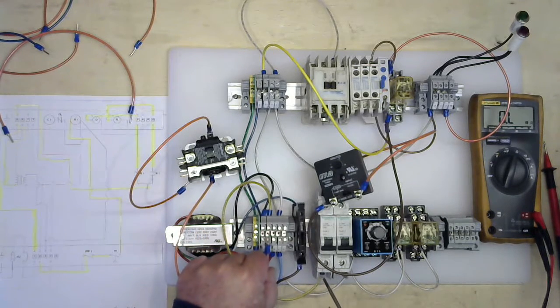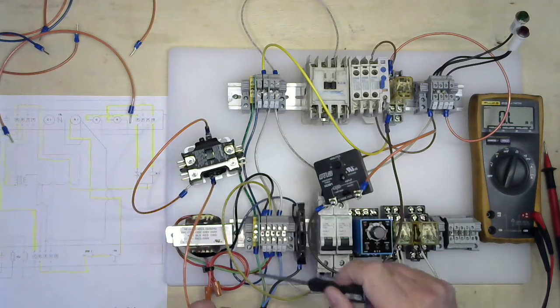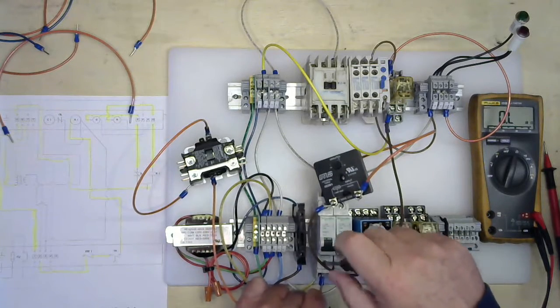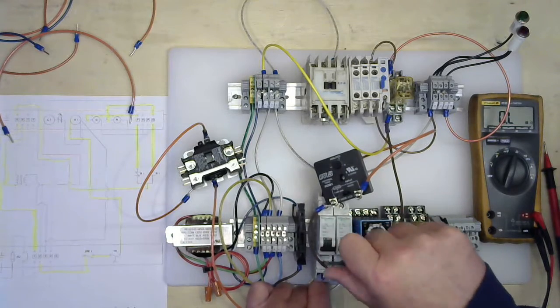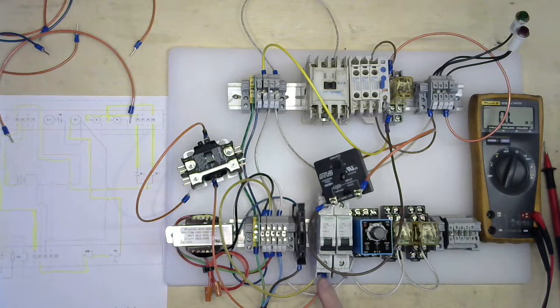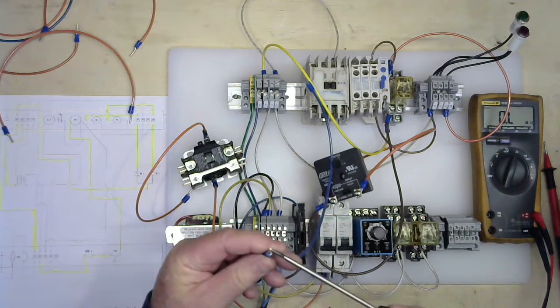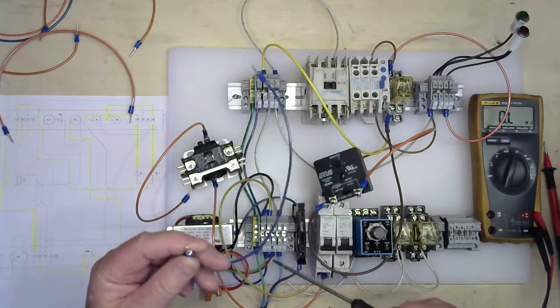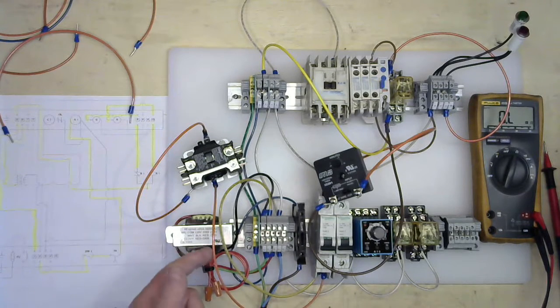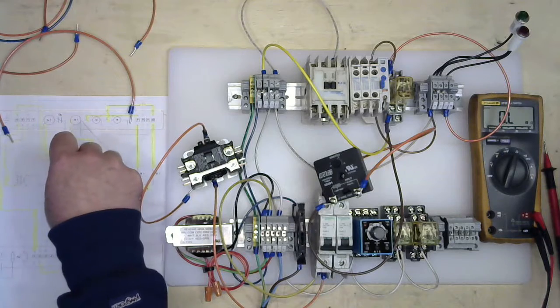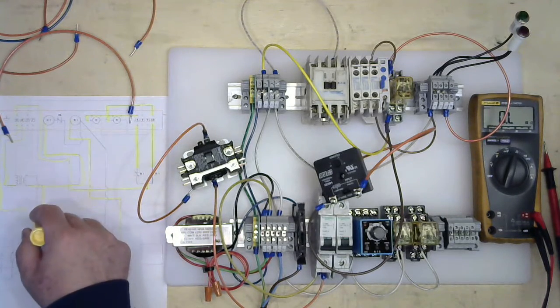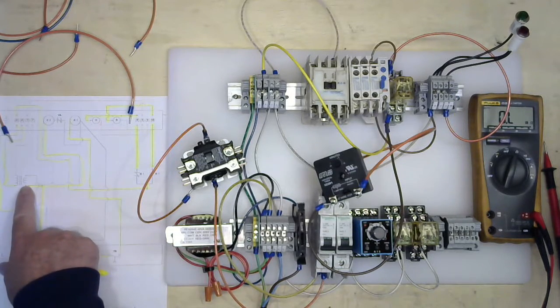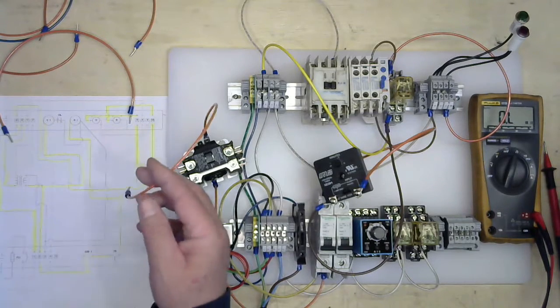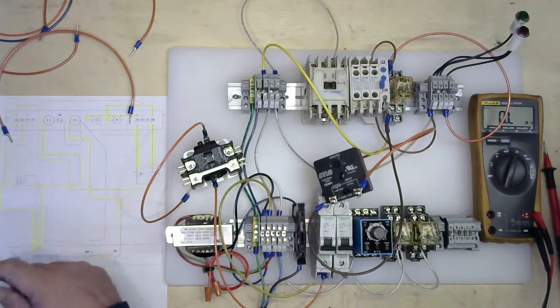I can try to fit this wire onto here. It's going to be a little cumbersome. I know I have more room on this side, and right now this is my primary side coming in. So instead, I'm going to jump over here real quick and coming off the switch. So I have more room on the back side of my switch than I do on my terminal block, because the pins we have here, diameter with these terminal blocks, usually made for 1 pin, a little harder on 2 pins. So even though I'm modifying the same concept, I'm sticking 24 volts from here into my transformer, or my coil, or my contactor. So I have that connected, and I know my transformer is already pre-connected here on the secondary side, so that's connected. Now I have to take my neutral out of the contactor into my overload.